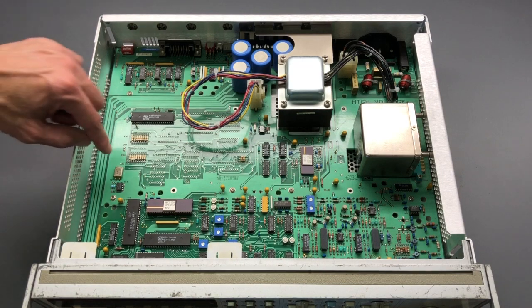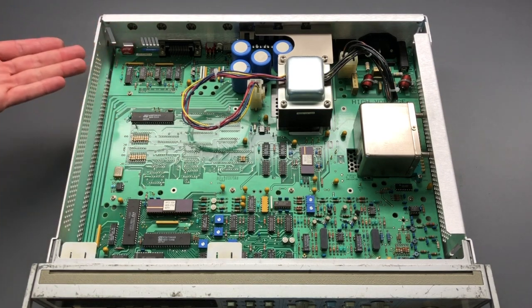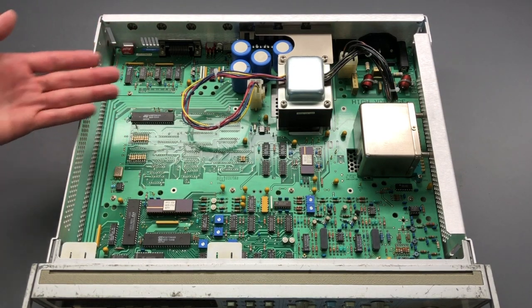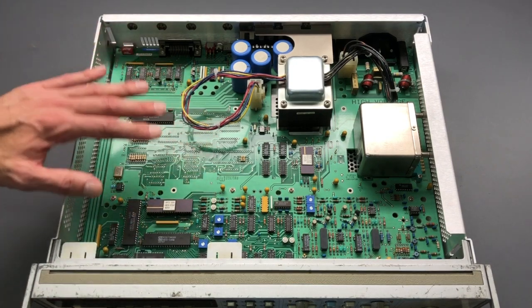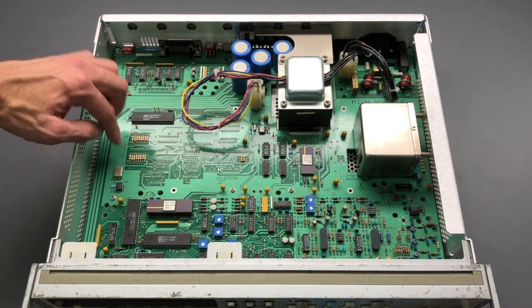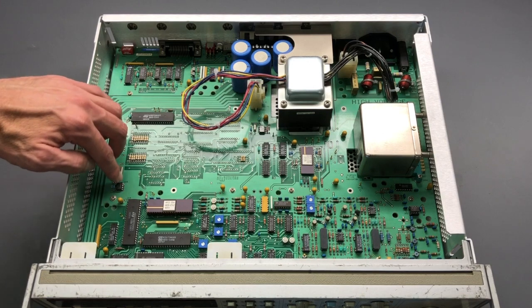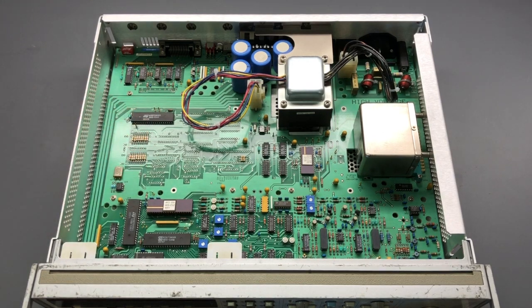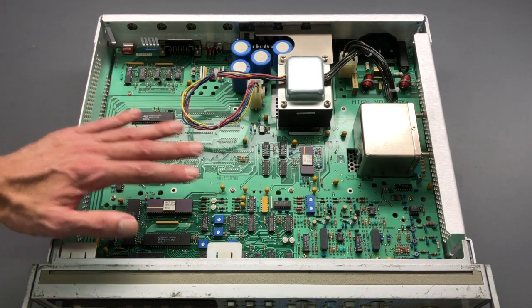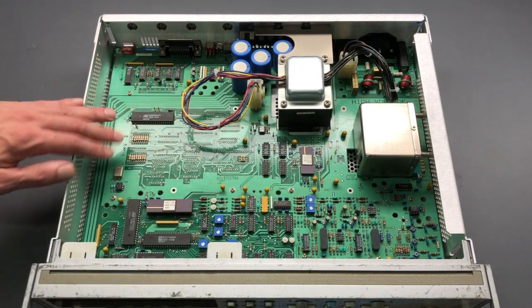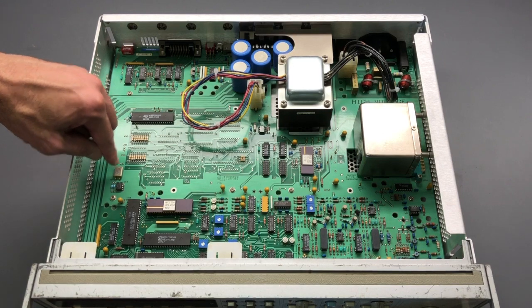But this crystal is of course exposed to the ambient air temperature that's inside the instrument, so as the instrument warms up, air temperature changes. This can vary a little bit, the circuitry around it can shift a little bit in frequency. Some circuits can tolerate that. It may not be a circuit that's having an effect on the accuracy of the instrument. So that's perfectly fine. You'll often see crystal oscillators that are just like this.